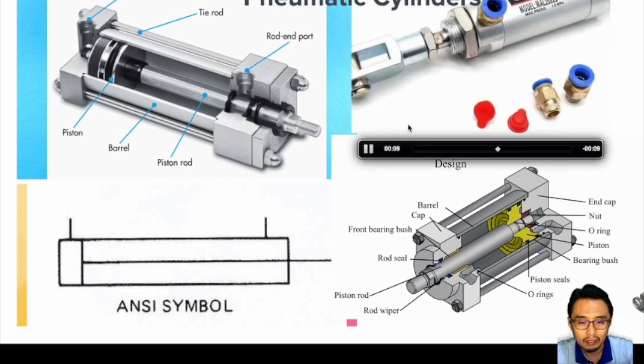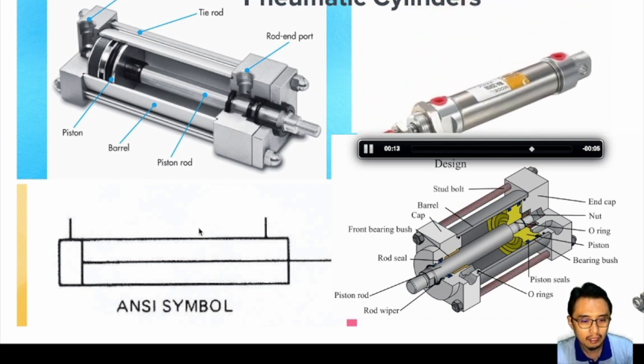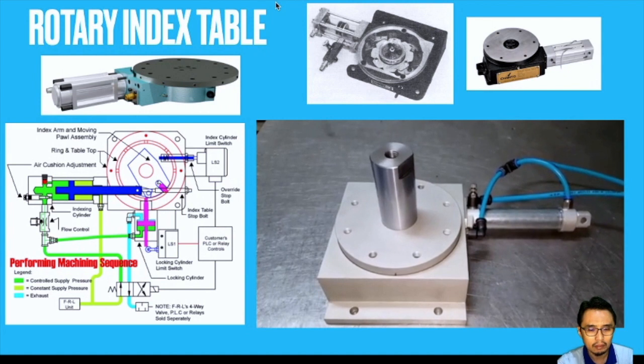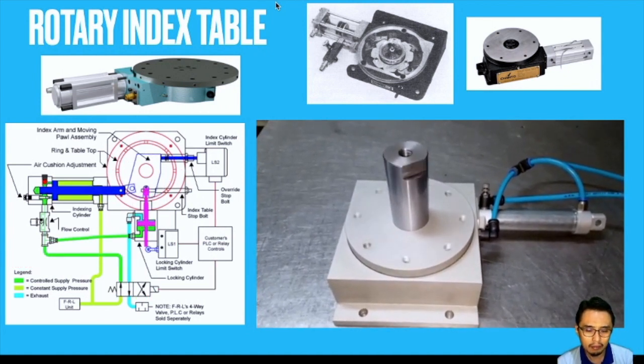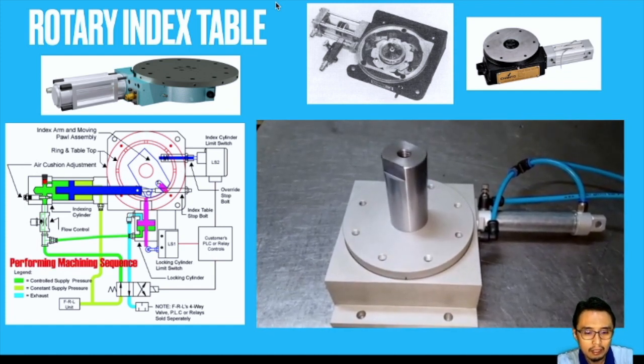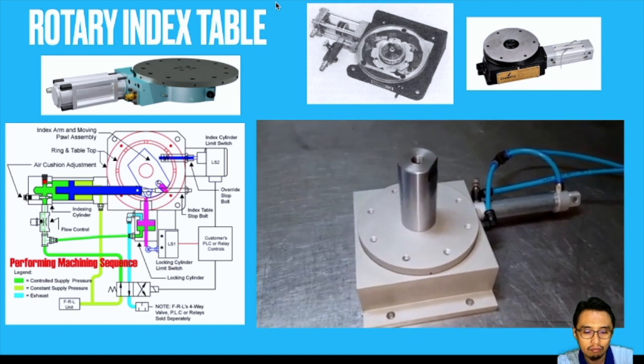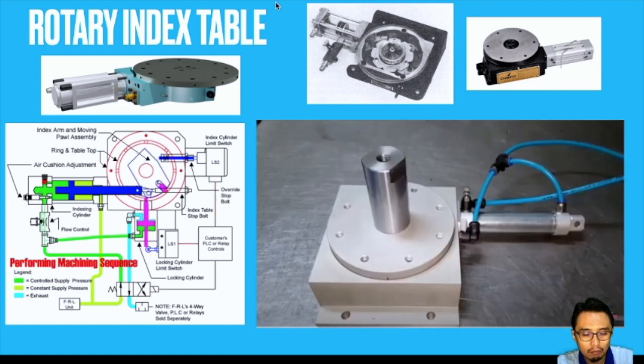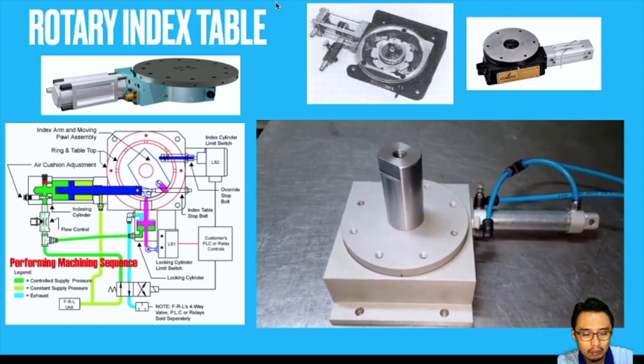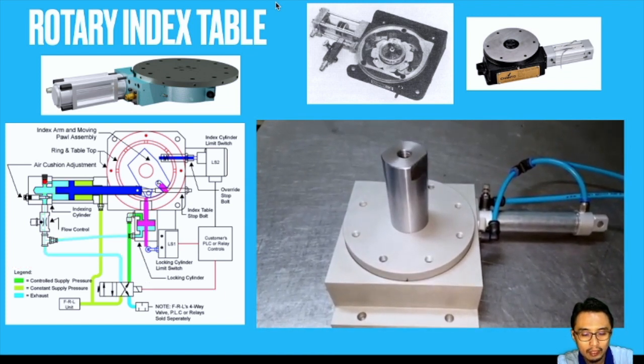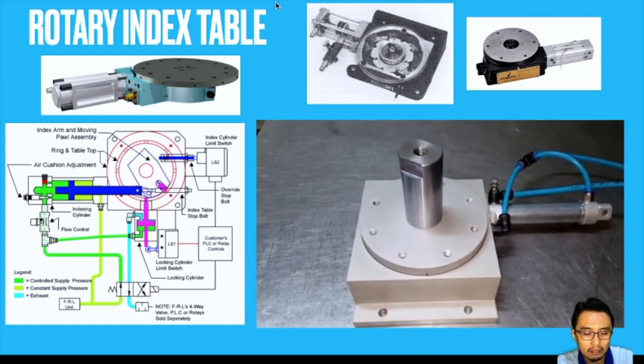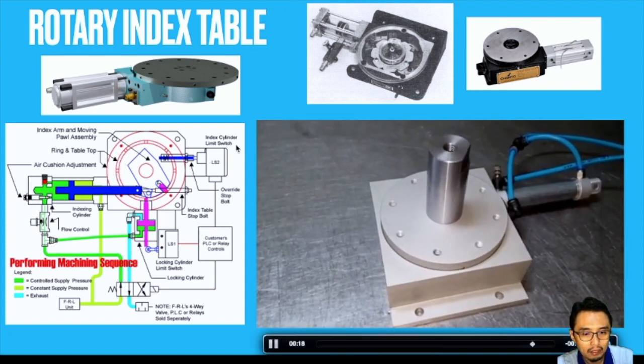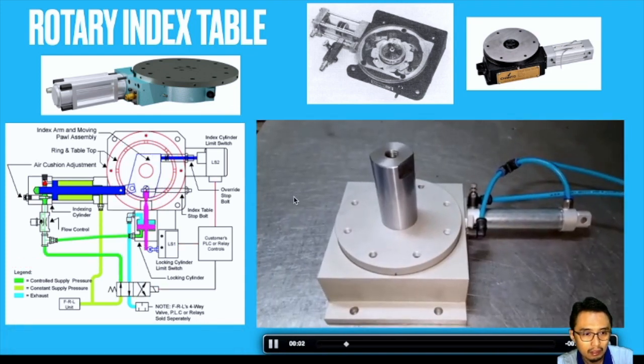These are examples of several different types of pneumatic cylinders with the ANSI symbol shown. Next is the rotary index table. The table is driven by a double-acting pneumatic cylinder. The inlet pressure can be adjusted to provide exact force for moving the load and to prevent damage in case of accidental obstructions. A rack and gear drive transmits the straight-line motion of the air cylinder to rotary motion with full power throughout its cycle. Through the use of different cams, the table can be indexed in 90, 60, or 15 degrees. These are several different examples of available rotary index tables.